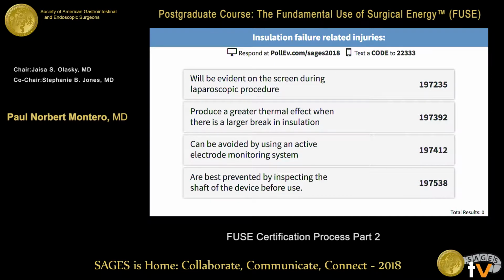Insulation failure-related injuries: 1, will be evident on the screen during laparoscopic procedure. 2, produce a greater thermal effect when there is a larger break in insulation. 3, can be avoided by using an active electrode monitoring system. Or 4, are best prevented by inspecting the shaft of the device before use. An important question.